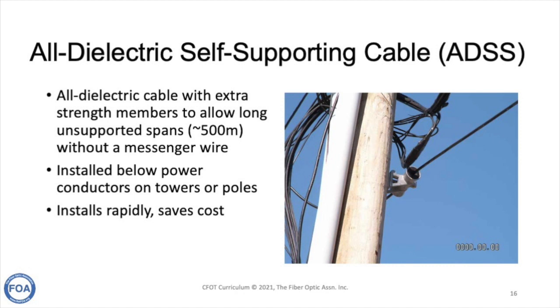A type of fiber optic cable often used for expanding communication networks along transmission lines is All Dielectric Self-Supporting cable, or ADSS. This cable has extra strength members to allow long unsupported spans on the order of half a kilometer without a messenger wire. With no messenger wire, there are no concerns about conductivity or grounding. It's installed below the power conductors on towers or poles, installs very rapidly, saves cost, and is very popular for expanding communications along transmission lines.